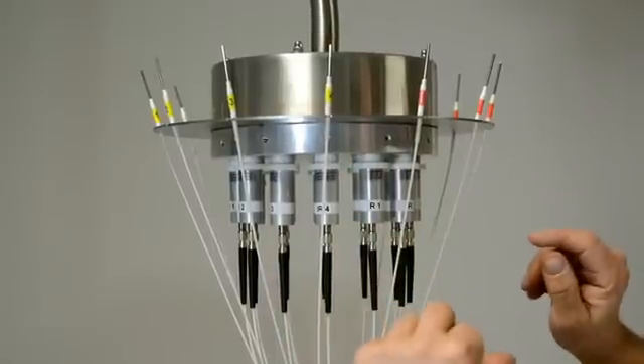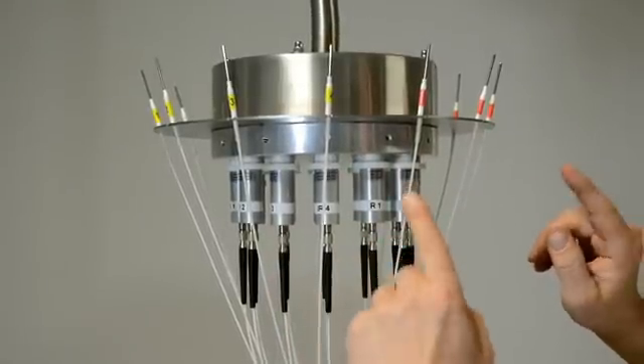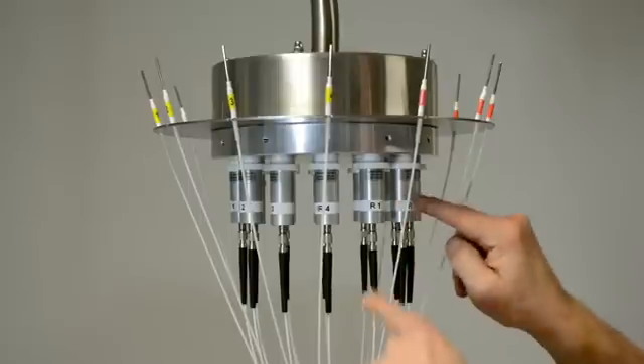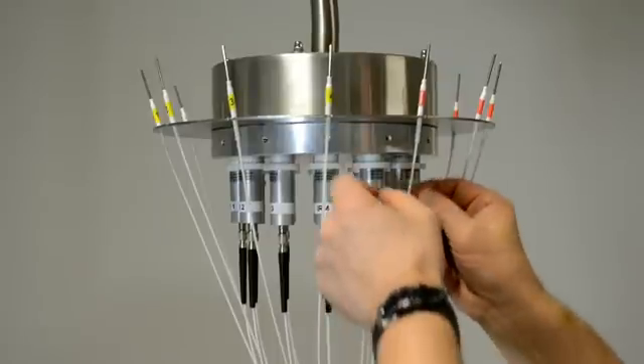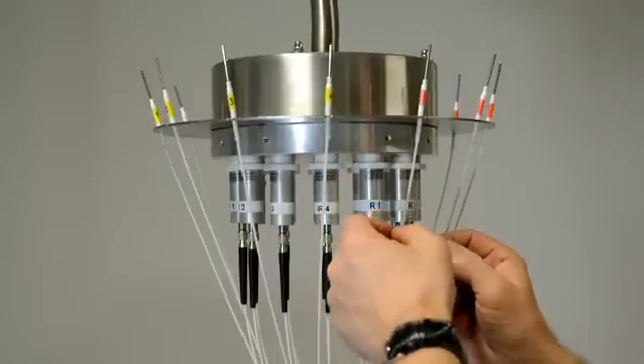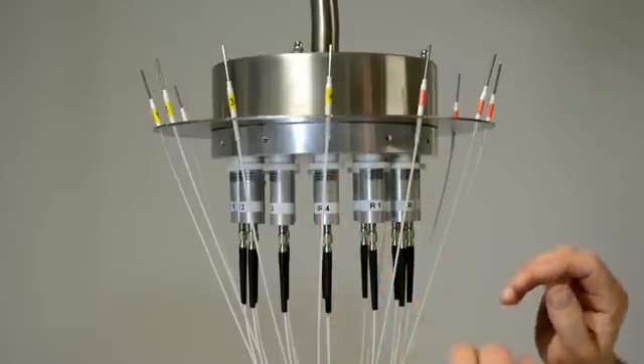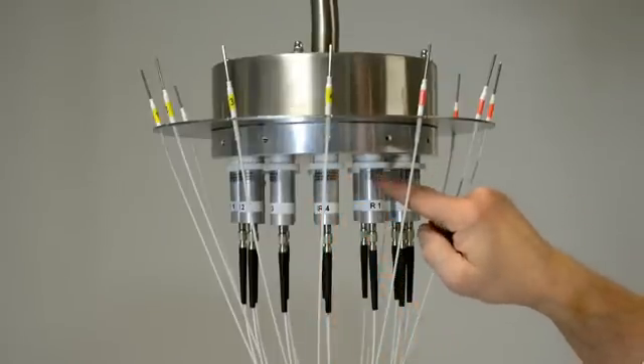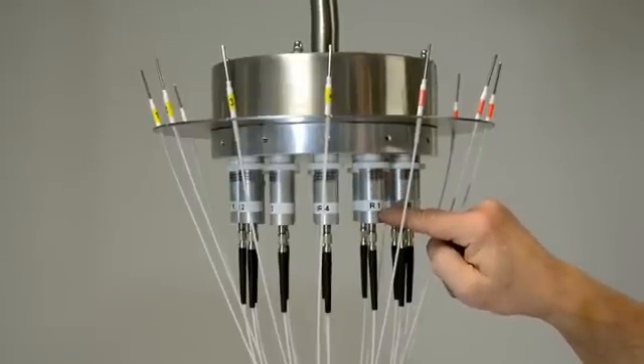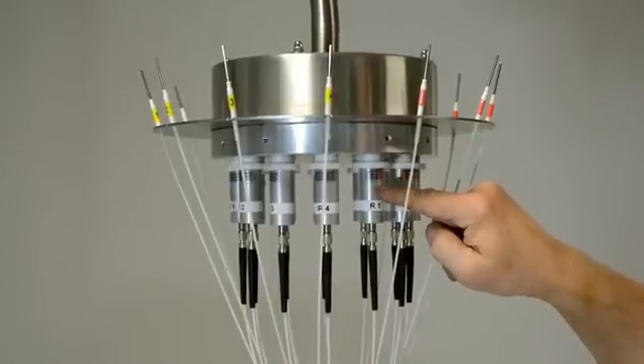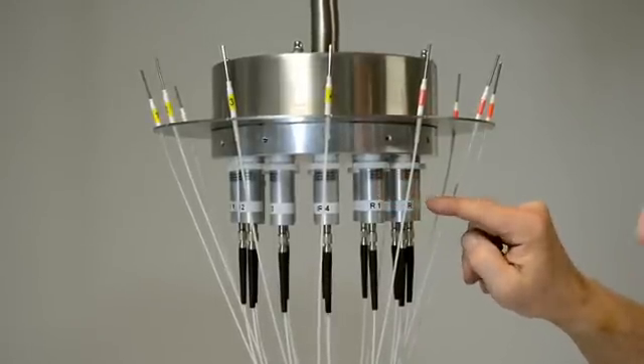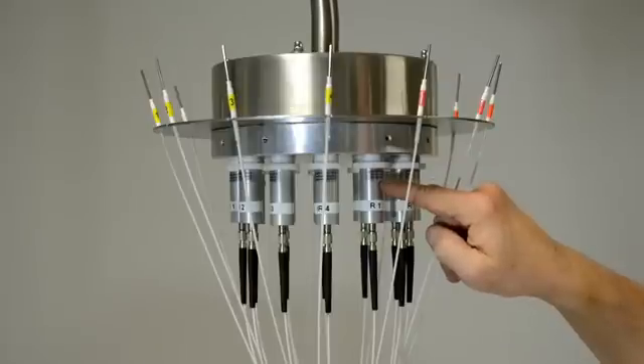Here you see the special metal head. The laser modules are fixed in a solid metal plate in the head of this laser device. The big advantage is that the modules are not inside the device, so if something goes wrong—maybe a diode is broken or fiber is broken—we don't have to open the device. We can remove and replace easily the laser modules on the metal head or replace the optical fibers.